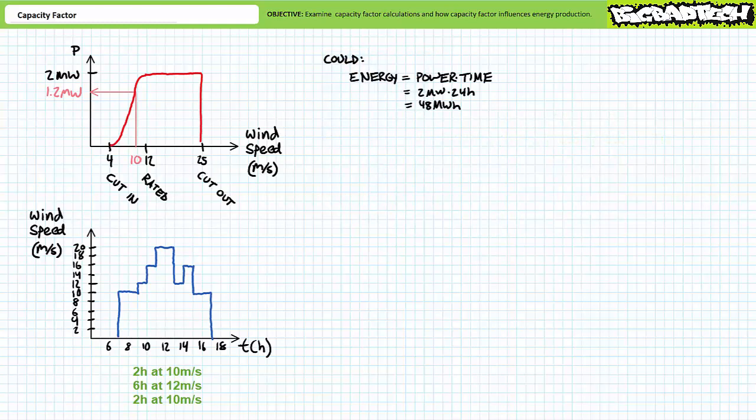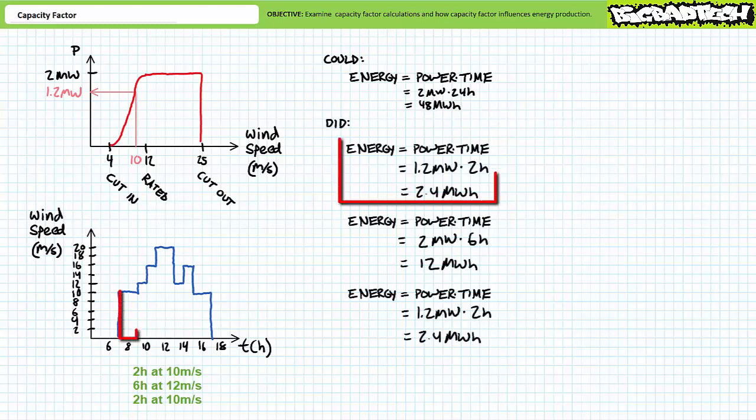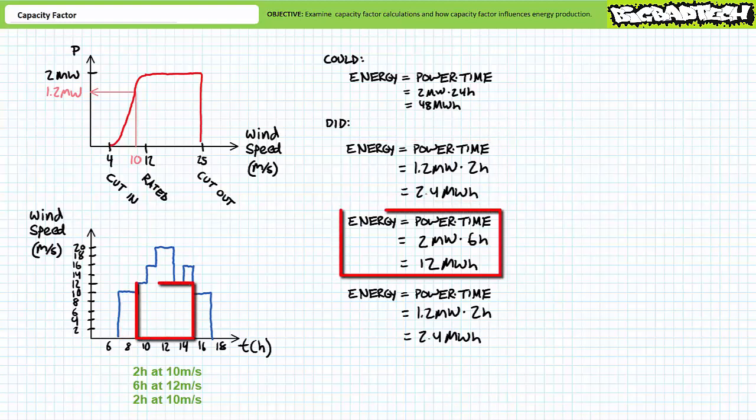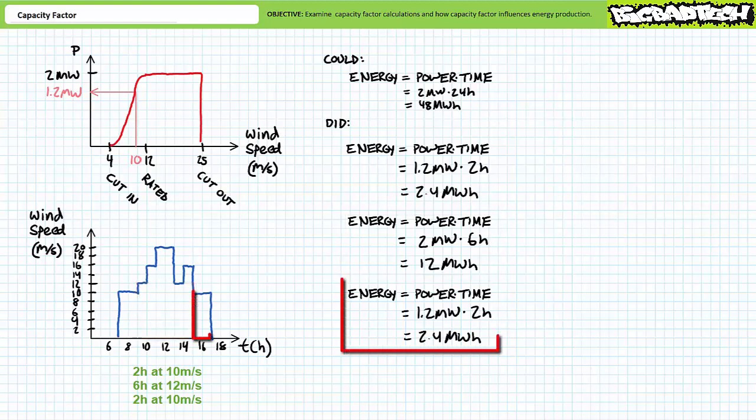Theoretically, a two megawatt turbine running at full capacity for 24 hours a day will produce two megawatts times 24 hours or 48 megawatt hours of energy. In actuality, this turbine produces less. For the first two hour period of 10 meters per second wind, the turbine produces 1.2 megawatts times two hours or 2.4 megawatt hours of energy. For the middle six hour period of 12 meters per second or greater wind, the turbine produces two megawatts times six hours or 12 megawatt hours of energy. Finally, for the last two hour period of 10 meters per second wind, the turbine produces 1.2 megawatts times two hours or 2.4 megawatt hours of energy.